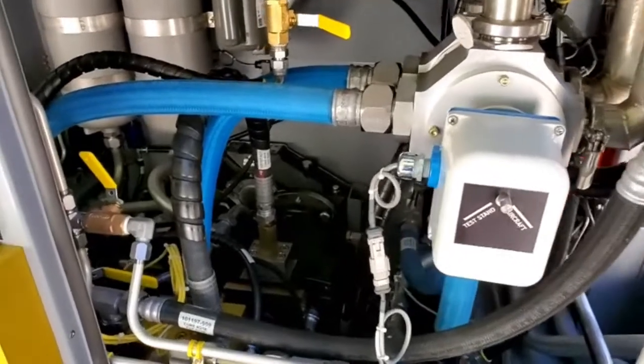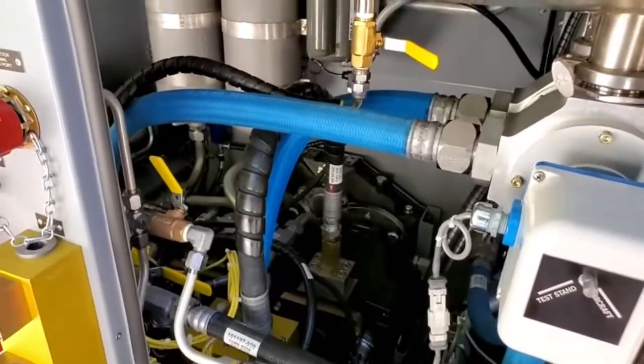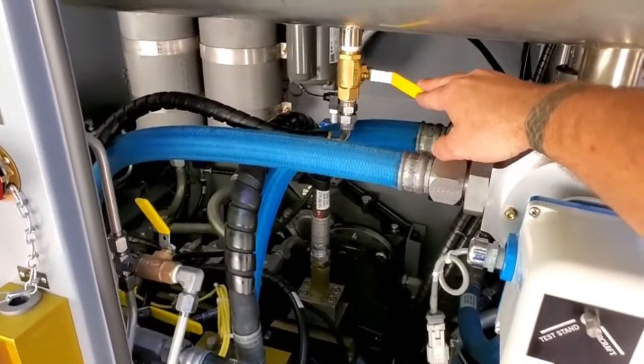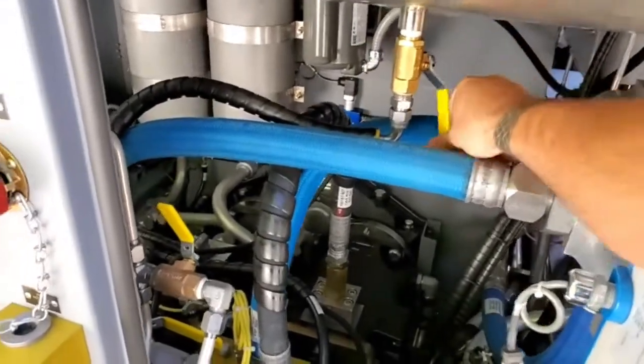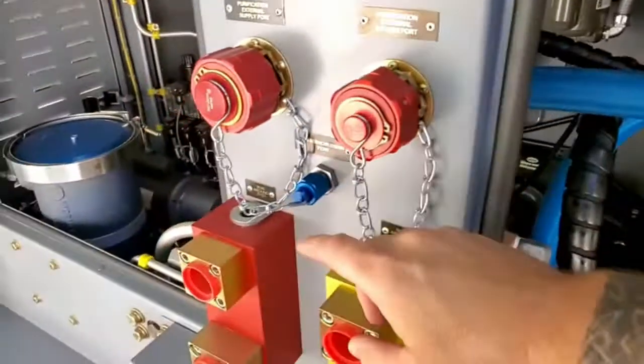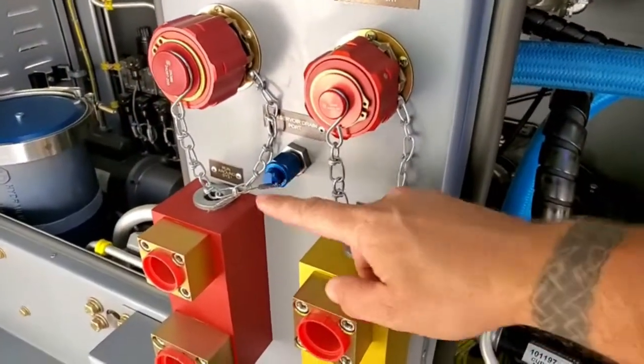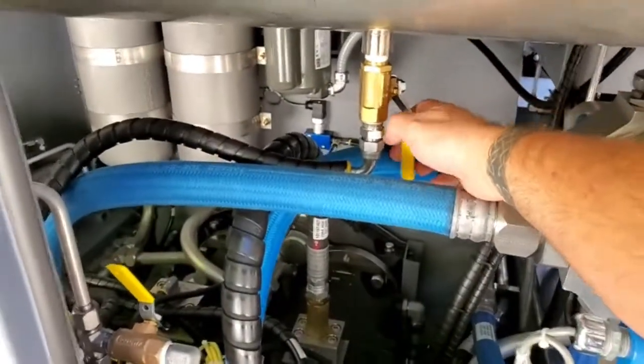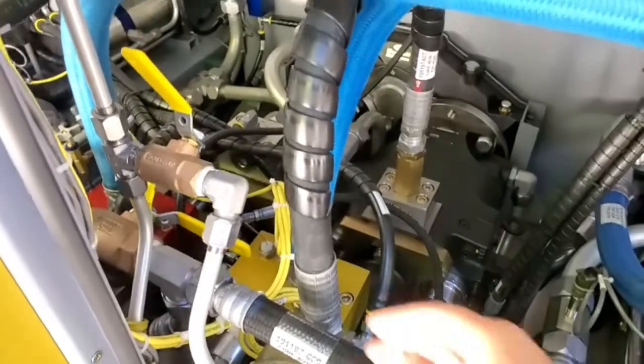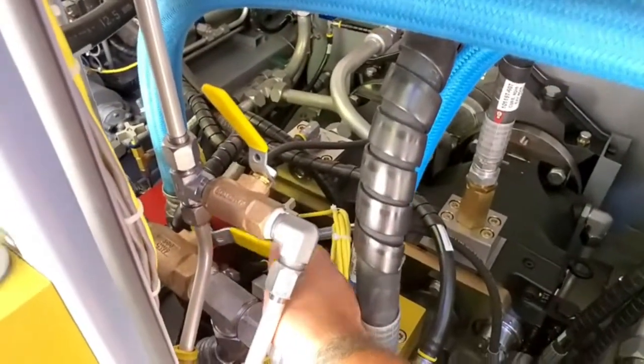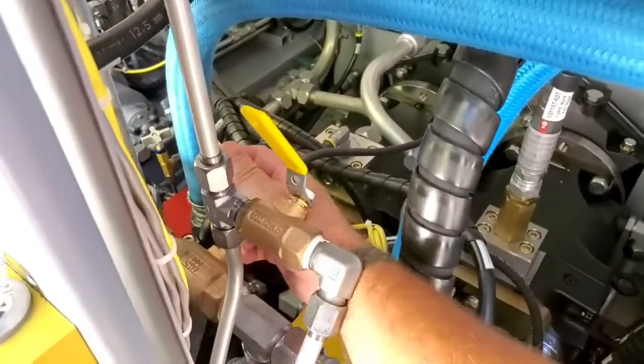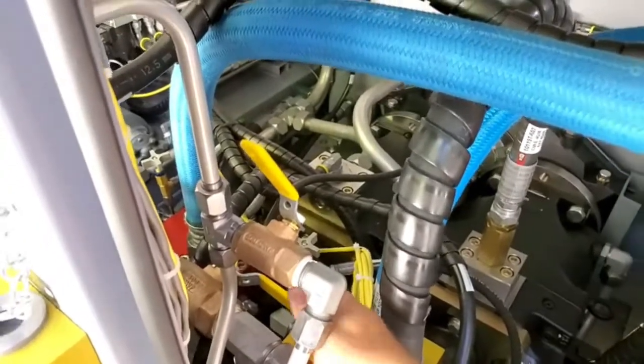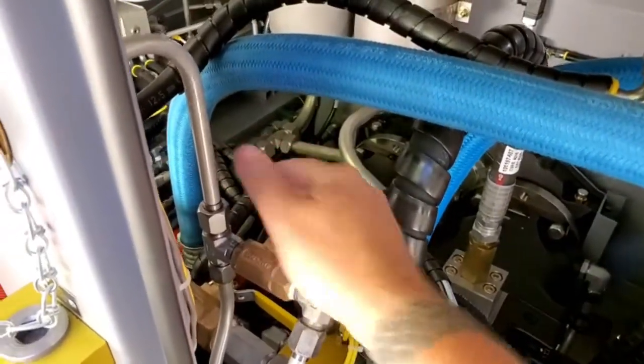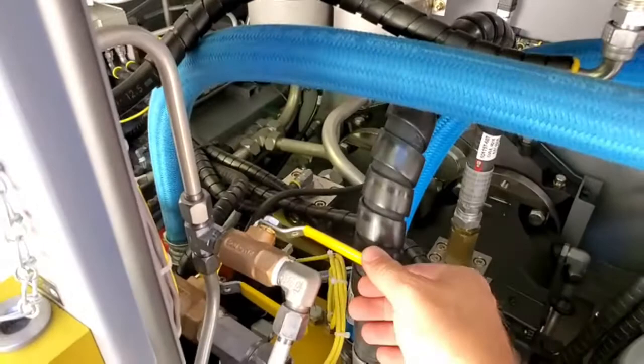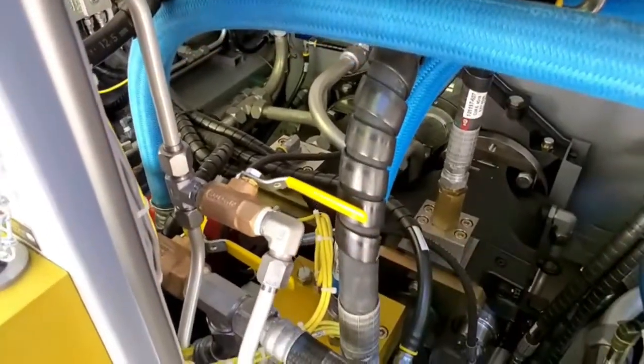On the diesel, you have 3 more valves. This is your reservoir drain. When you open this, you can drain your reservoir through this port right here. This should remain closed at all times. And then you have 2 more valves here. This is your purification supply shutoff valve, currently closed, should be open, and your purification return valve, currently closed, should be open.